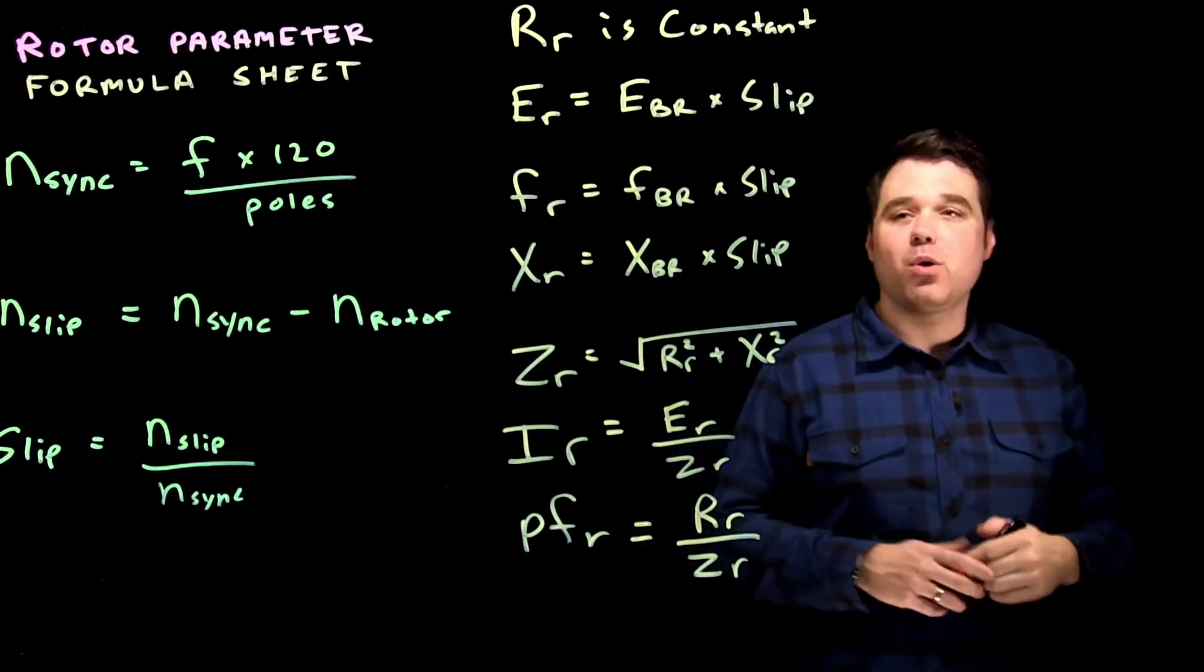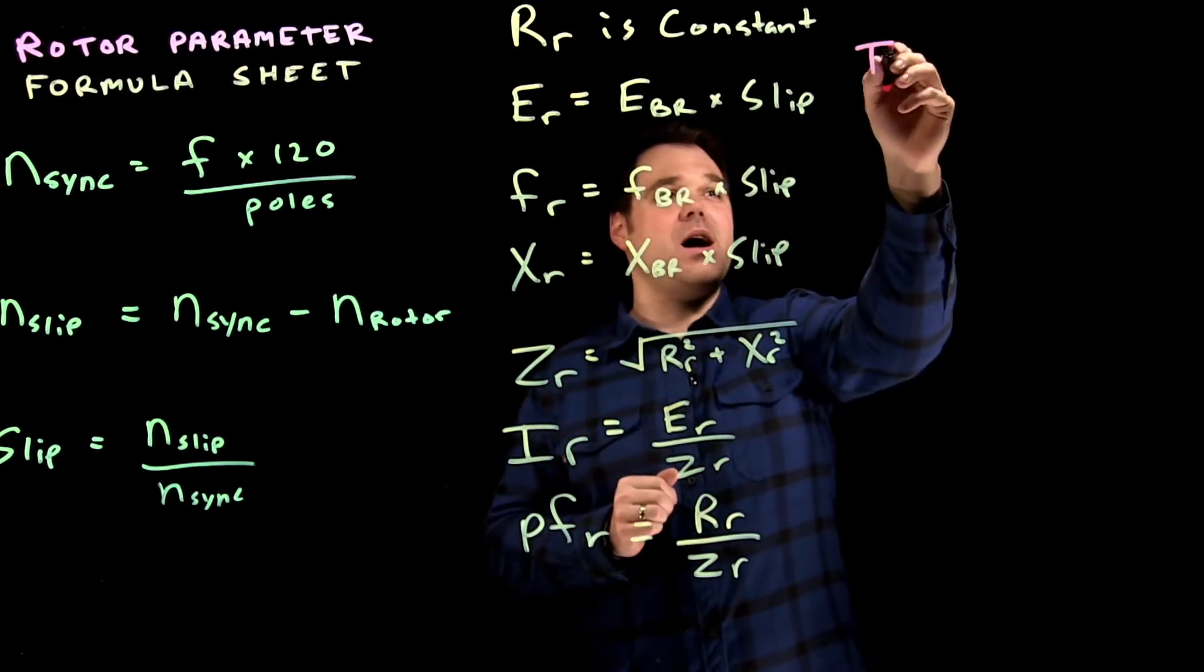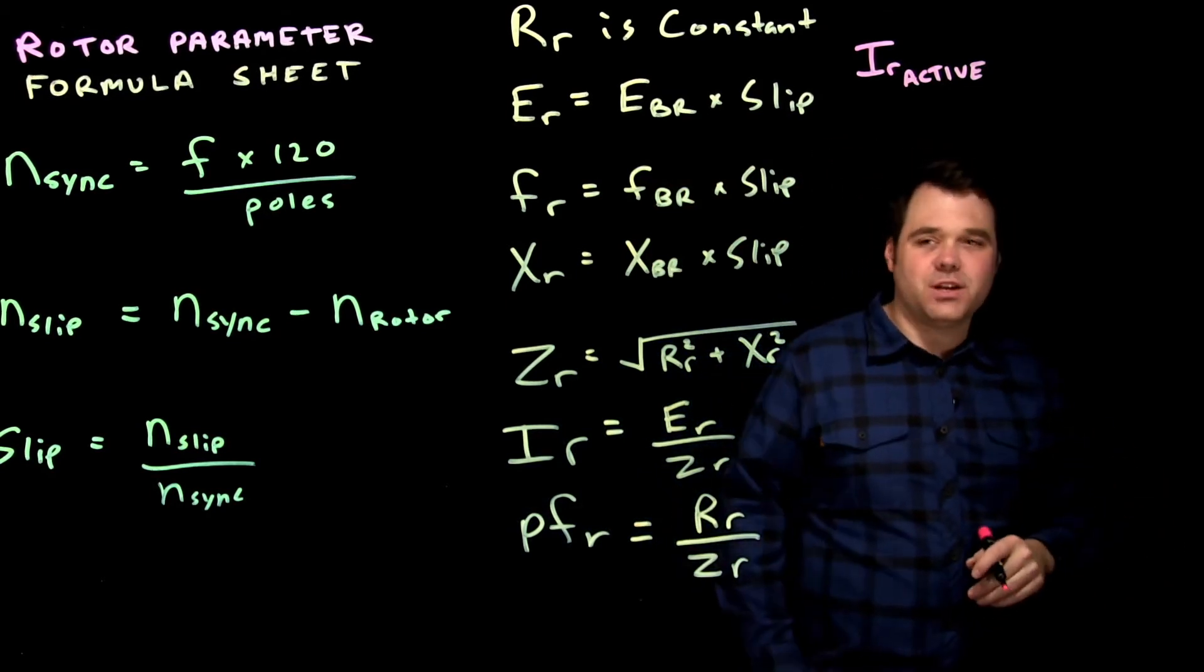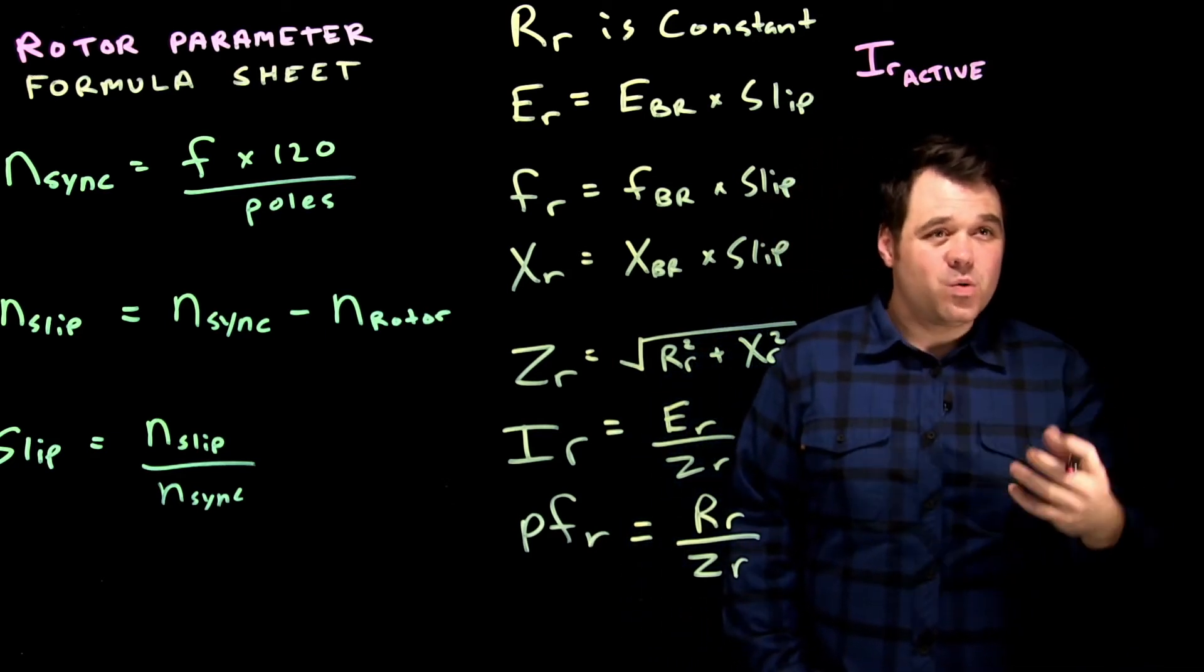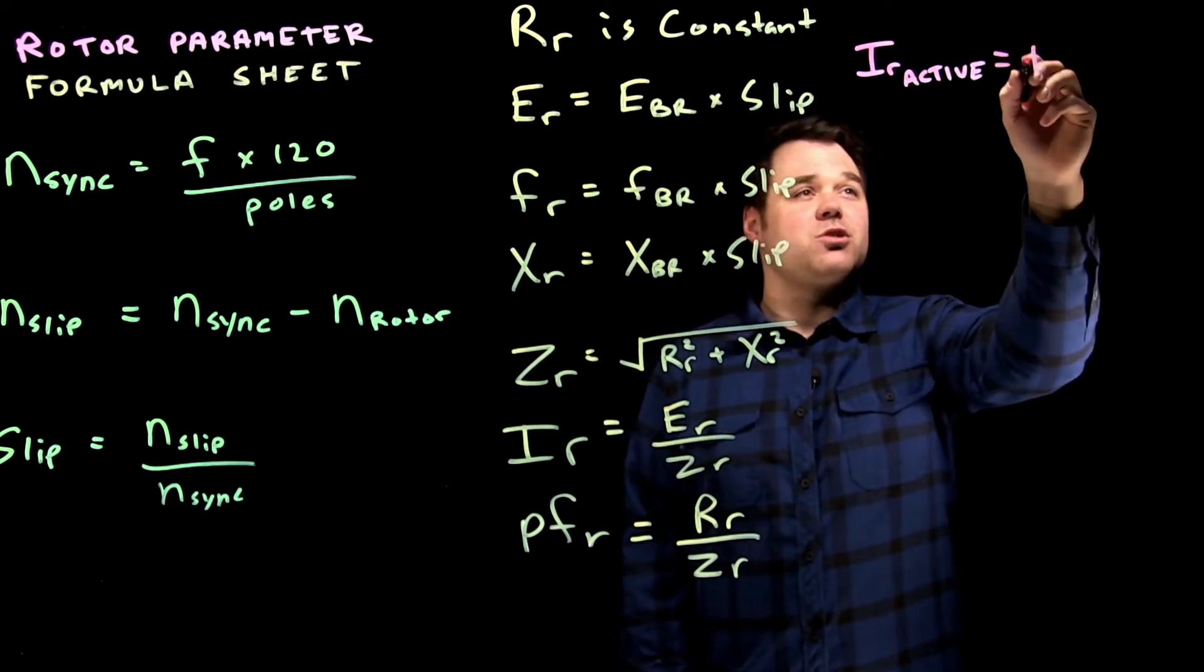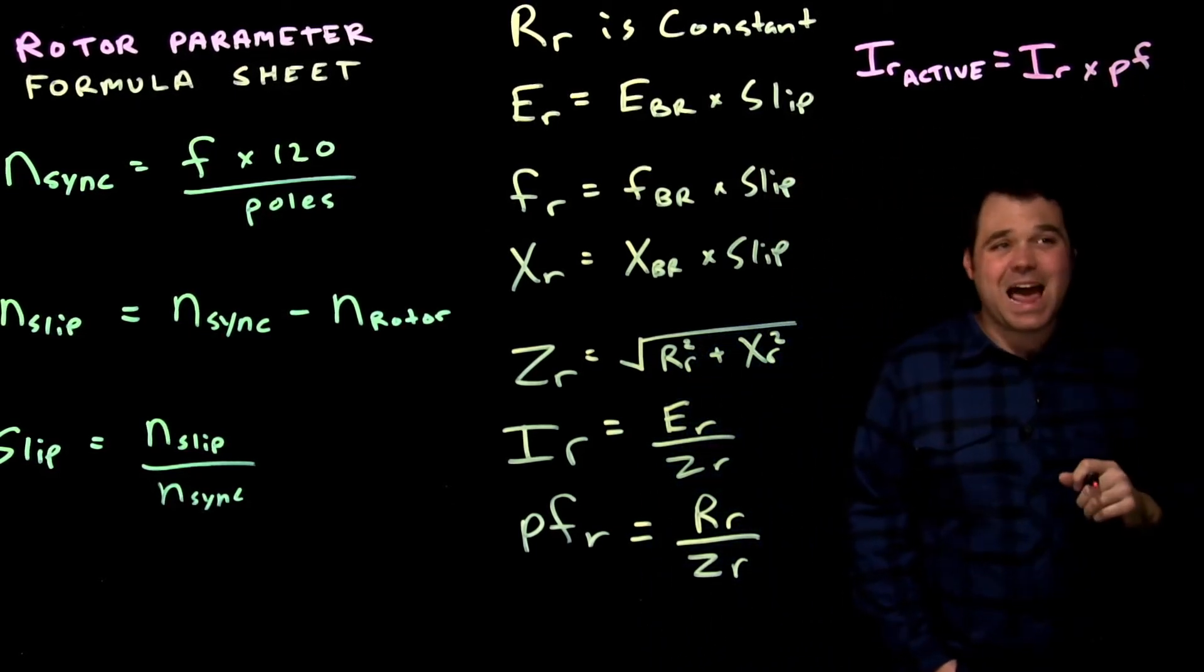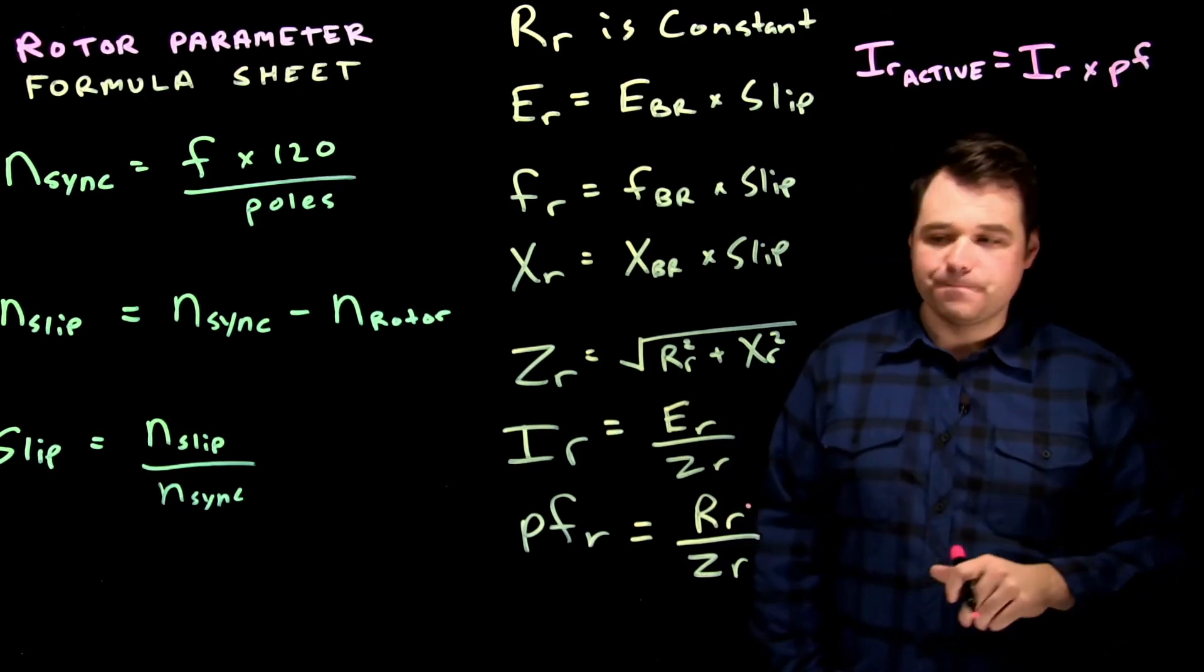So what's most important inside a rotor is what we call the active current, right? So we can call it the IR active, or IRR, you'll see a bunch of different things. But this is the actual current inside the rotor that is generating torque. It's the one that's getting that rotor to spin. So we're going to take the total current of the rotor, multiply it by our power factor. That's how we get the active current because it's the in-phase component, or what would be that resistive component there.